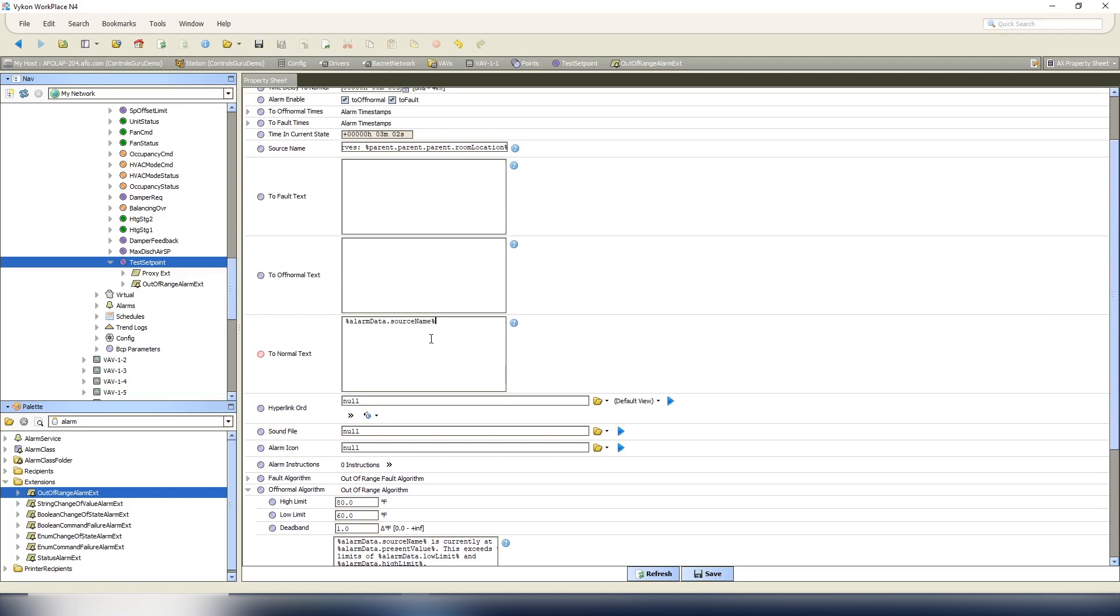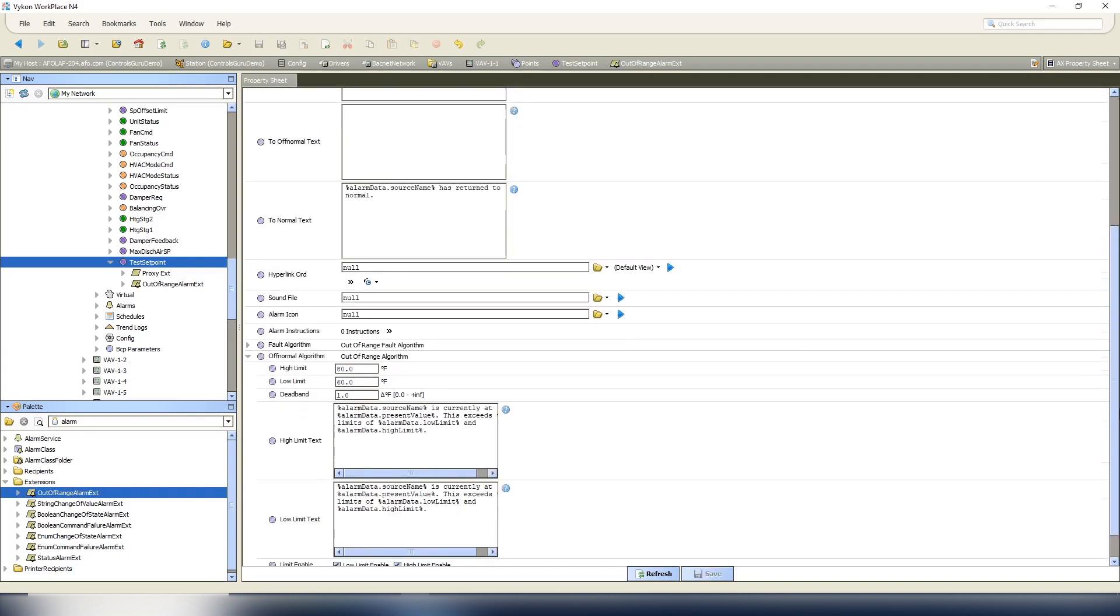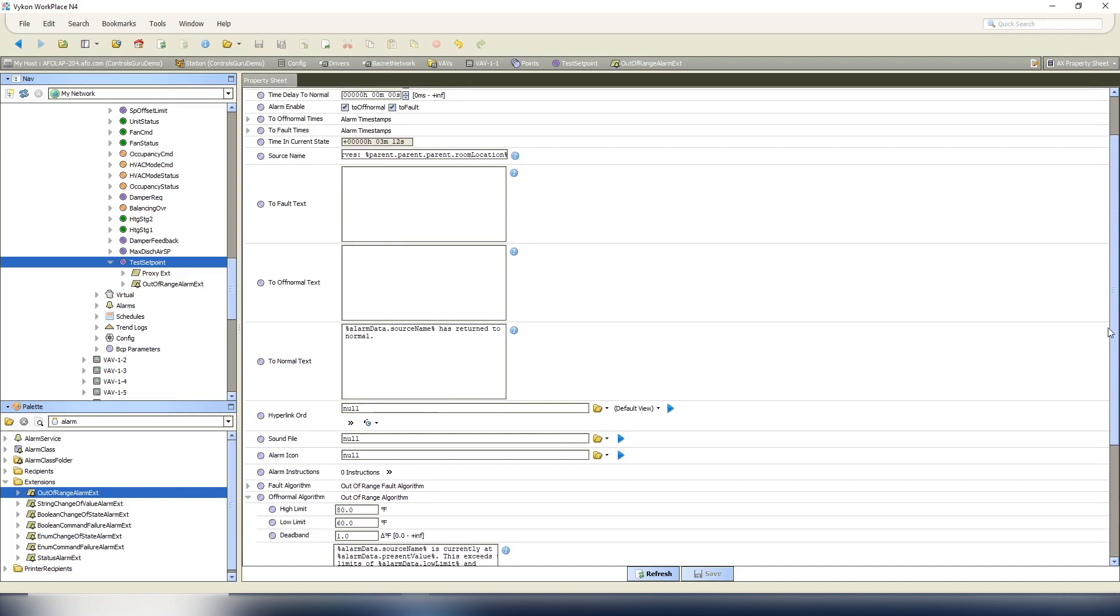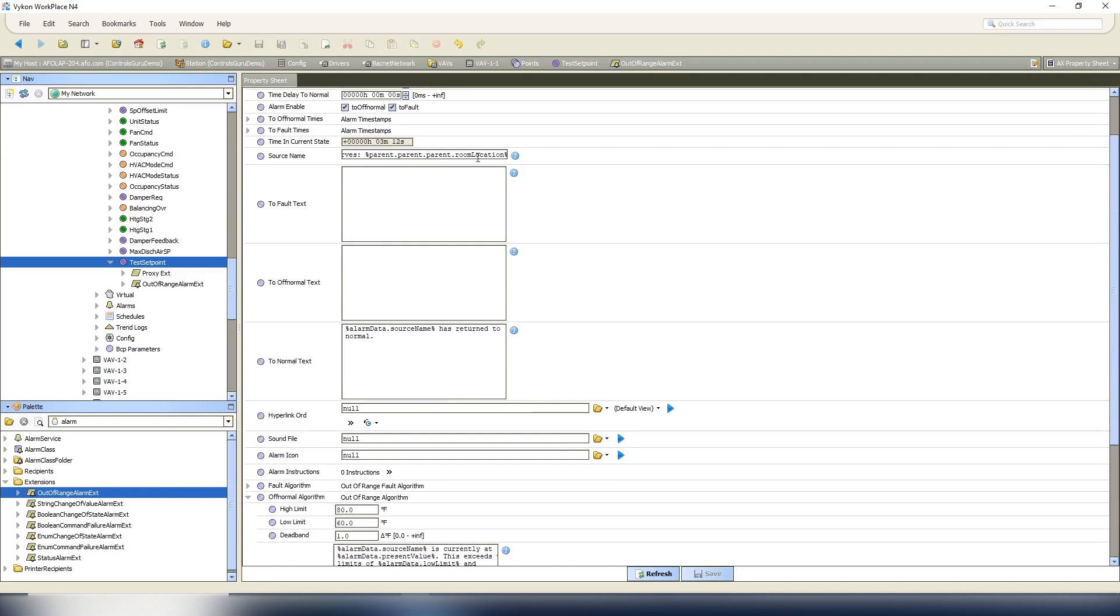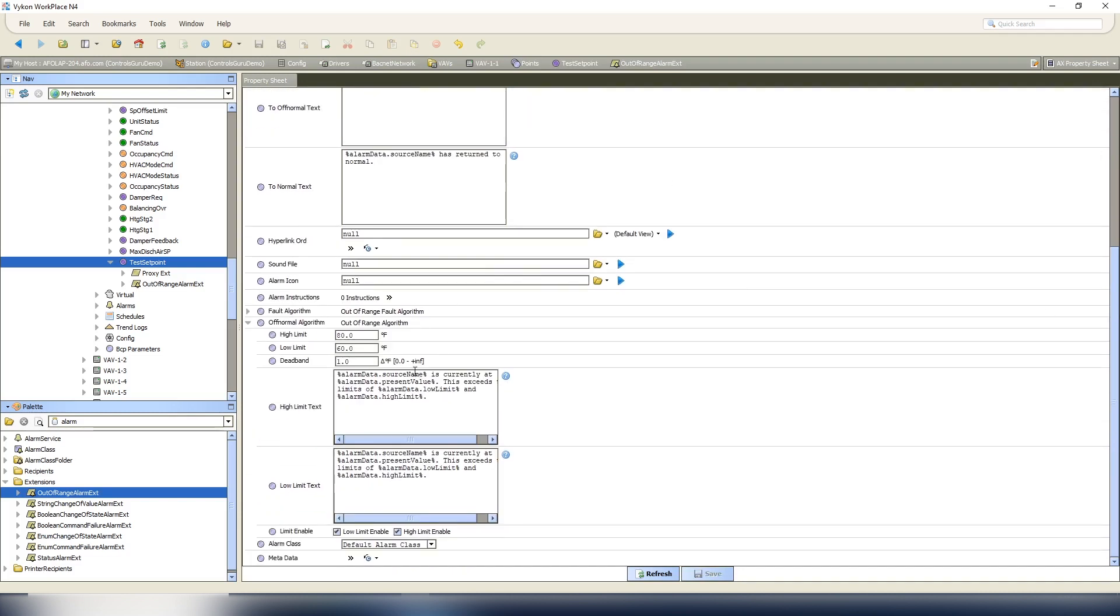So then we can go up here to our normal text and we can say alarm data dot source name has returned to normal, and we'll save that point. So now we set up our alarm points with all our information. We've got the room location in here and this source name is going to reference that same room location.